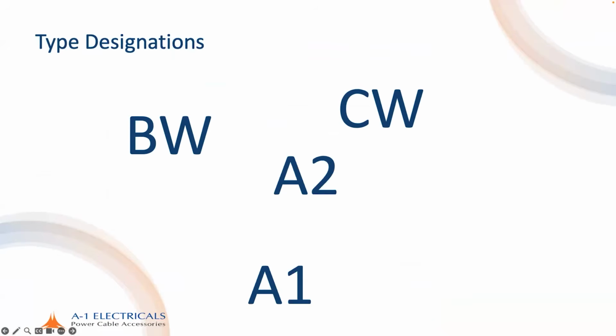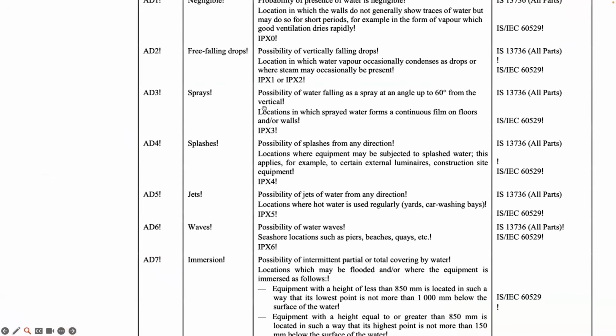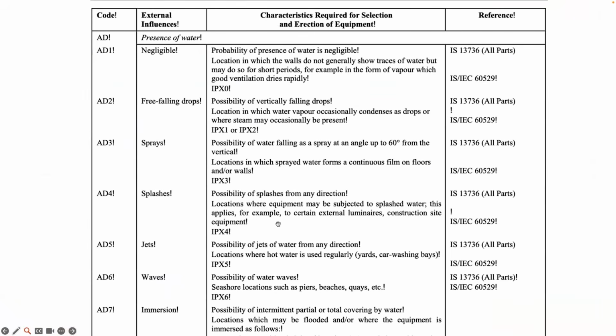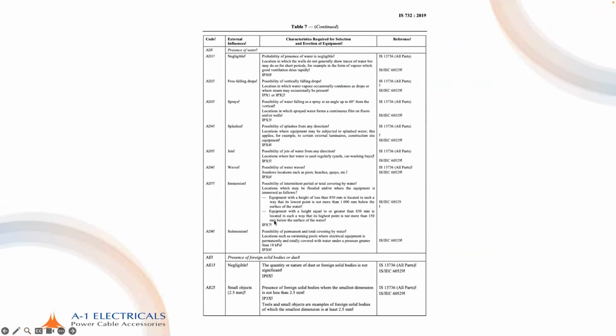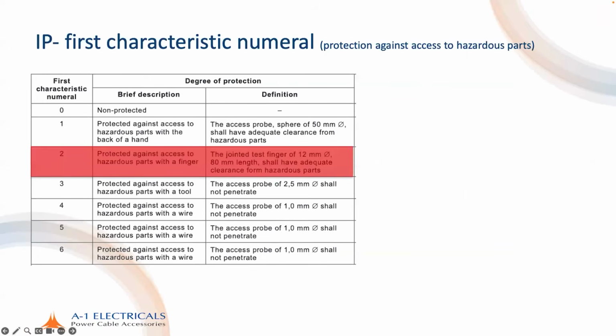What is the external influence in this table? Sorry, just a second, I'll go to that slide. This table. Once you figure out, for example, that you need IP66, we know that a gland that conforms to the requirements of IEC 62444 has to have a minimum amount of ingress protection, correct? And we know that is to be IP54. Beyond that, what you need depends on the gland. You need to talk to your manufacturer and ask them what the level is.